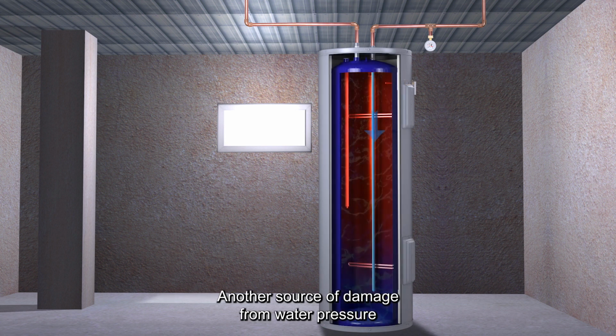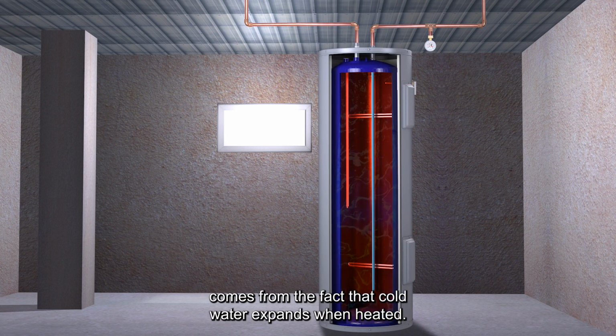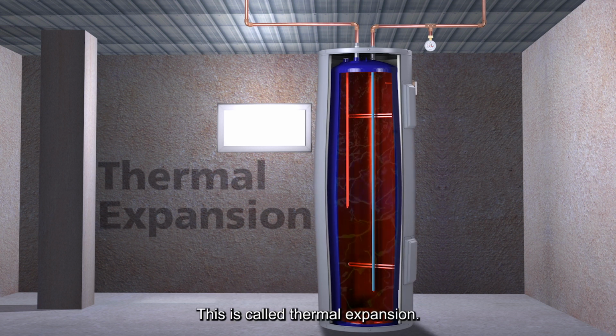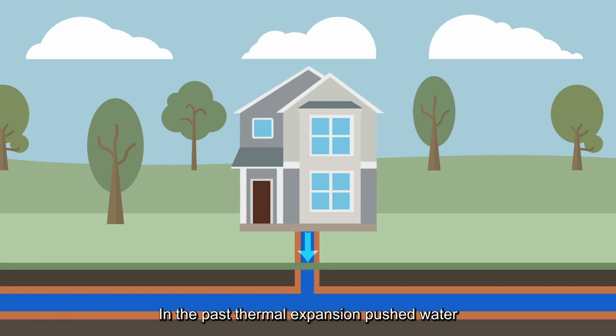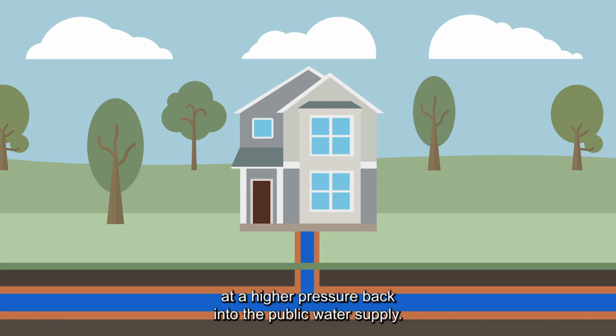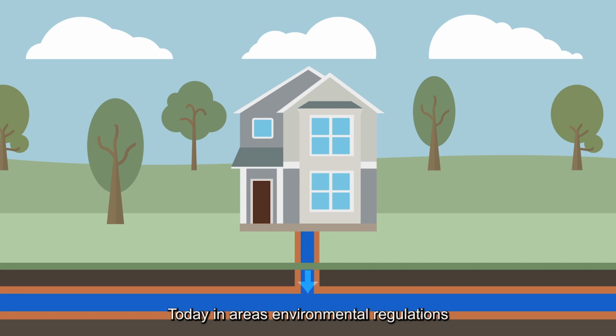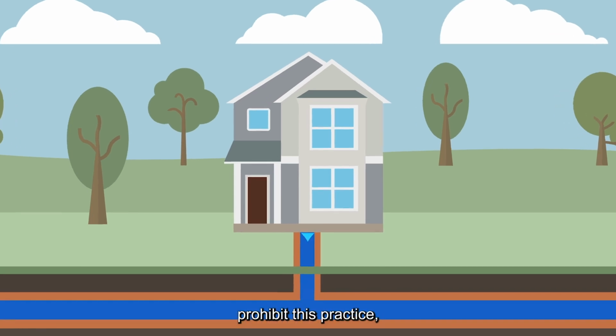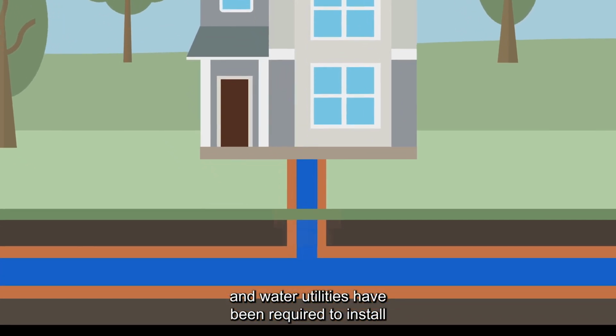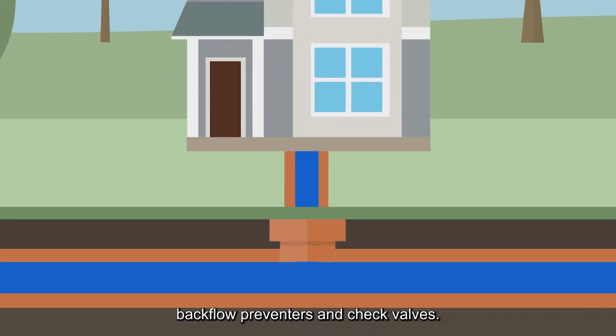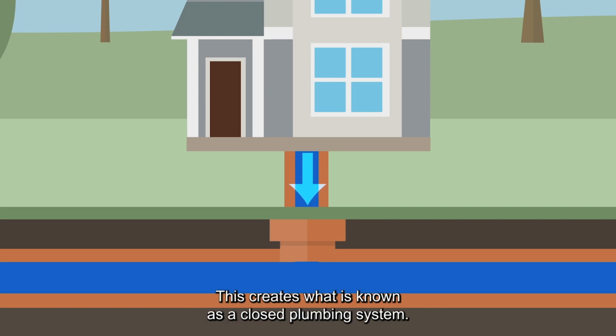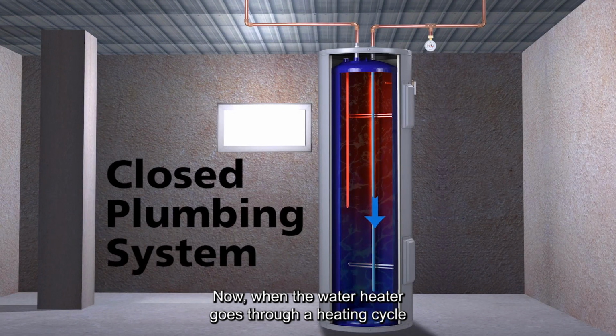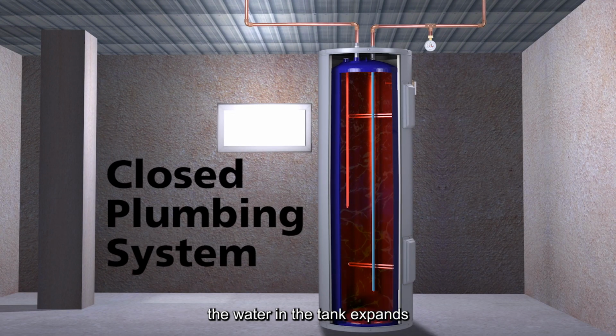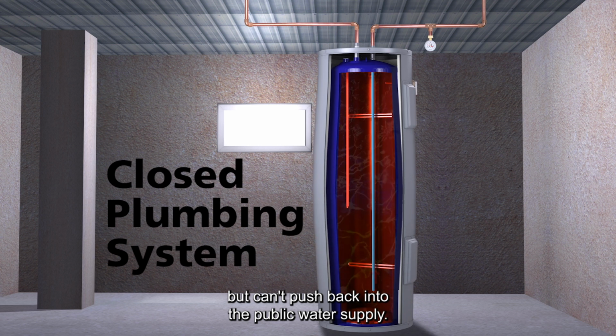Another source of damage from water pressure comes from the fact that cold water expands when heated. This is called thermal expansion. In the past, thermal expansion pushed water at a higher pressure back into the public water supply. Today, in most areas, environmental regulations prohibit this practice, and water utilities have been required to install backflow preventers and check valves. This creates what is known as a closed plumbing system. Now, when the water heater goes through a heating cycle, the water in the tank expands, but can't push back into the public water supply.